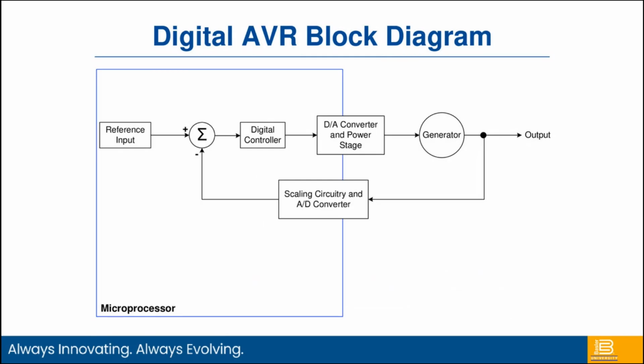So, the digital voltage regulator block diagram. This is simplified, but it's a very similar approach to what an analog voltage regulator does, with a few exceptions. Again, we're looking at the output of the generator, and we're going to pull this into this A to D converter. There's some scaling circuitry. We're taking an analog signal now, and since we're working with a microprocessor, we're changing that analog signal into ones and zeros, or a digital signal. That digital signal is going to tell our summing point, very similar to the summing point of the analog voltage regulator, what the output of the generator is.